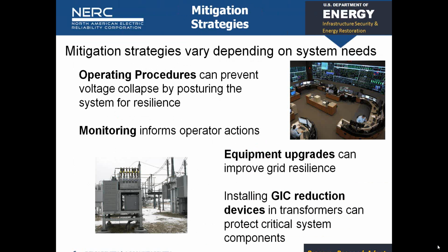That allows the operator to make better informed decisions. On the hardware approach also, there are equipment upgrades that can improve the resilience. For example, there are certain relay types that are less susceptible to GIC impacts than other types. And in the case of that March 1989 event, a situation where the relays cause tripping of reactive power support can be mitigated by understanding your relays and their susceptibility and making an upgrade there. There are also improved designs of transformers that are more resilient to GICs. And in many cases now, utilities replacing transformers are specifying certain GIC withstand capabilities and putting those into their procurement processes.